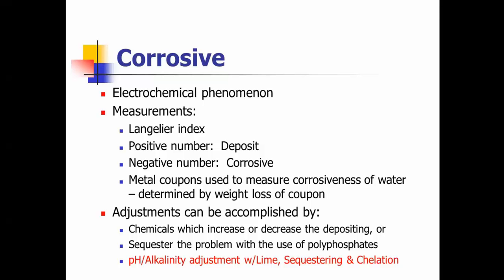Corrosiveness is an electrochemical phenomenon. They measure it with the Langelier index. A positive number means it's deposited. Again, a negative number means it's corrosive. They use metal coupons to measure the corrosiveness of the water. Adjustments, you can accomplish that by adding chemicals to increase or decrease the depositing. Sequester the problem with the use of polyphosphates, and pH alkalinity adjustment with lime, sequestering and chelation.